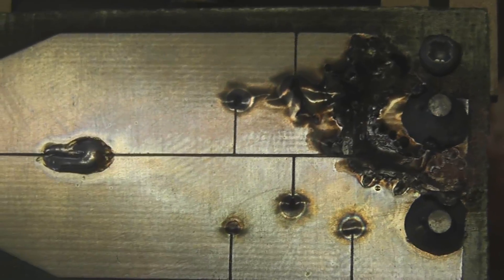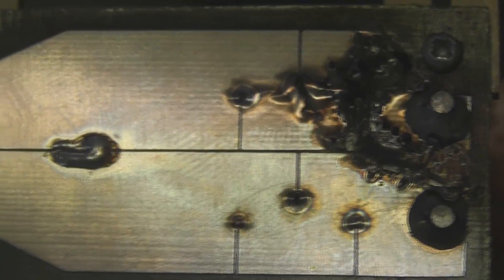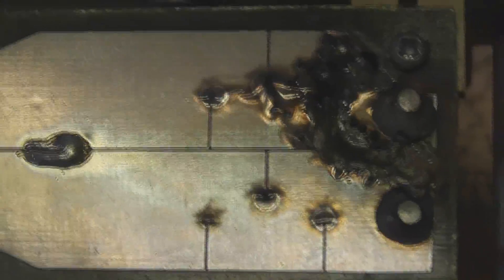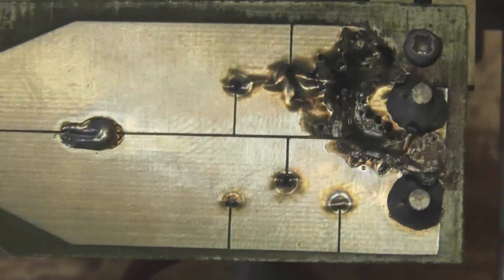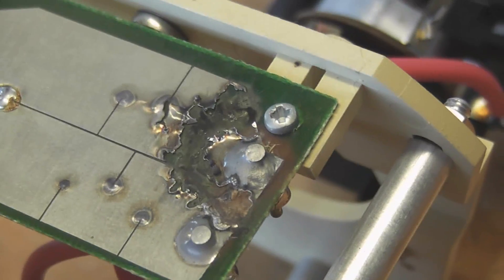This is the parallel shunt which has been subjected to excessive current flow. A few little thin hairlines in here, that is actually for calibration. But yeah, it has been exposed to severe overcurrent and it's gone open circuit.